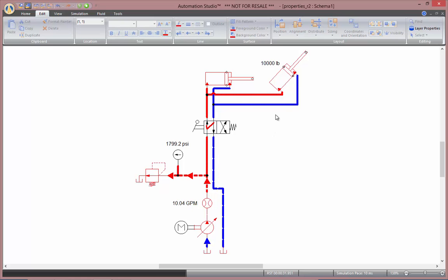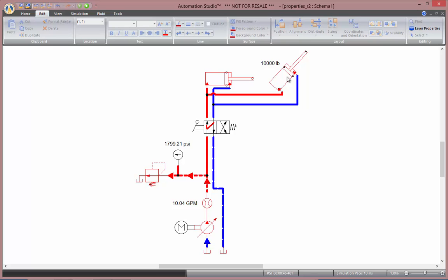Now, as I retract my cylinder, you'll notice that this line becomes purple, and we have negative psi. This is because the external load of 10,000 pounds will drive my cylinder in, creating some cavitation issue in my line, and that will be displayed with that purple color.